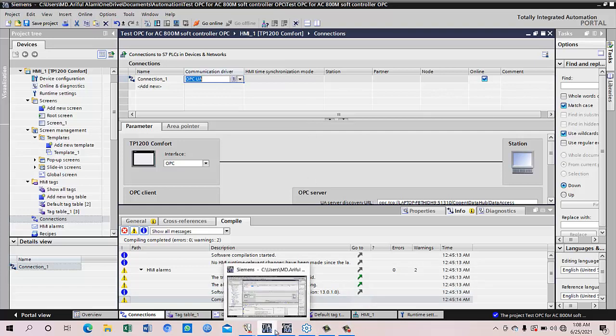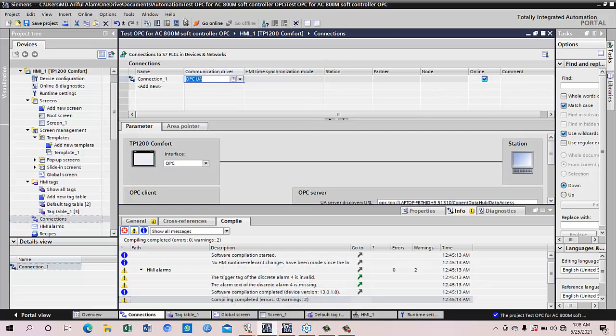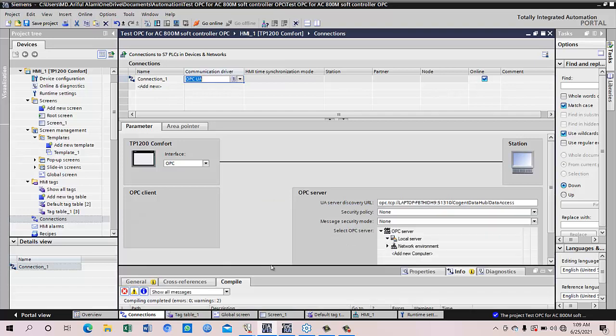So we need OPC DA and OPC UA conversion. That means data is collected from the soft controller by OPC DA AC 800M and we have to make an OPC UA that can receive data from the OPC DA and transfer to OPC UA. The HMI can connect to the OPC UA. So in here we need a bridge connection of the OPC and the conversion of the OPC from OPC DA to OPC UA, also from the OPC UA to the OPC DA.